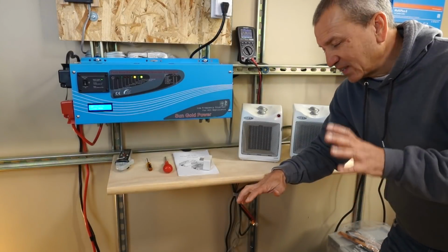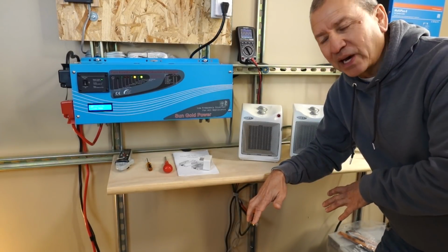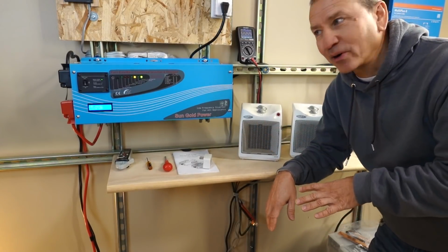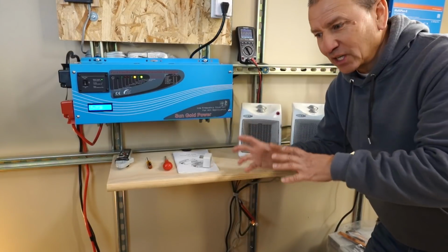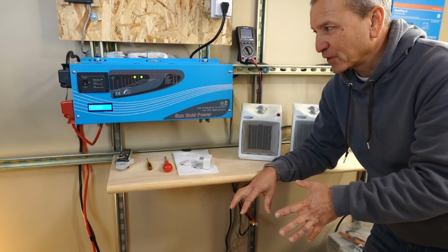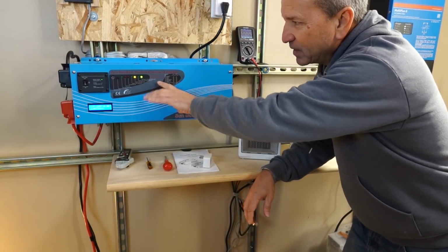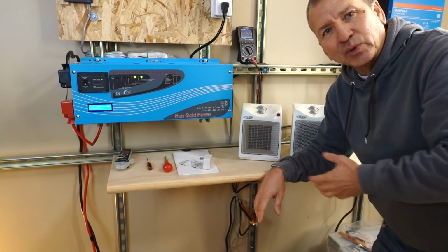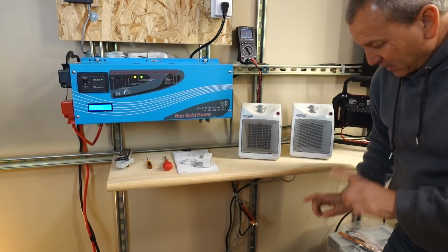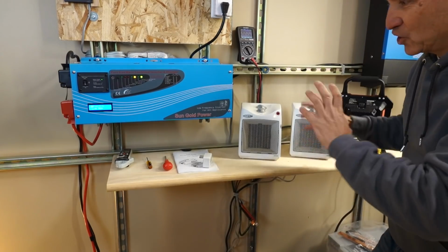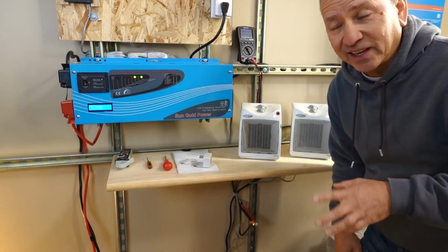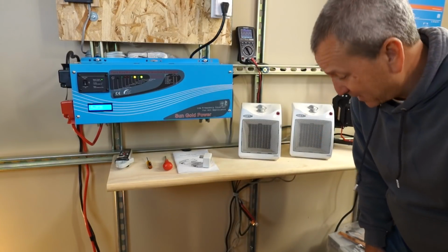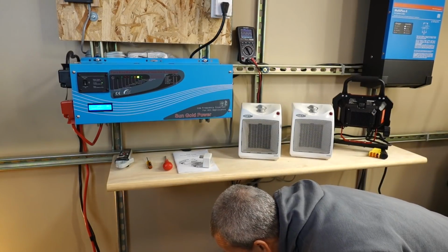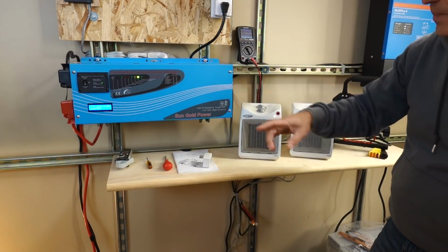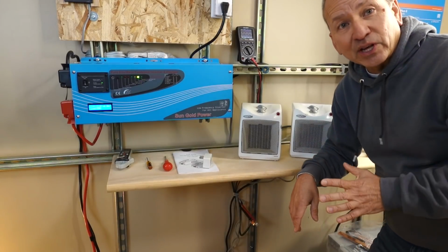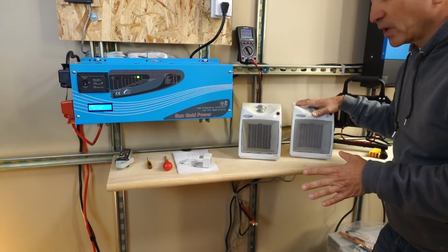Now what I want to do is simulate a loss of AC power. So we're going to shut off the AC power and let the transfer switch over to inverter mode. Right now it's charging the batteries and passing through the 120 volt AC, but I'm going to switch it off and it should switch over automatically. I think 8 milliseconds is what it takes. So off we go. Heard it beep. Pretty quick. Now what if we had some stuff running?